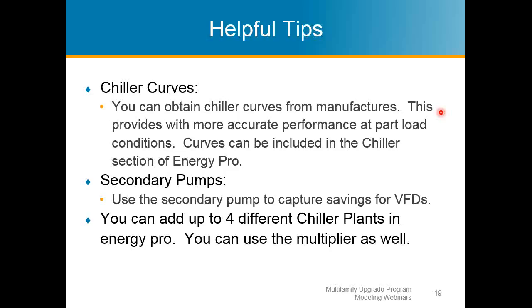Chillers come with chiller curves, so you can get chiller curves to satisfy part loads. Some are very similar to your variable refrigerant flow (VRF) systems, where they modulate down based on the load. A chiller can do the same thing, and it uses what's called a chiller curve to satisfy those part load demands and needs. So chiller curves can be put into EnergyPro. There's another tab basically under the chiller section called curves, and you're going to want to get that information from the manufacturer. Based on the system you have, you can give them the information you have for your set points, and they can provide you with a chiller curve to match that system.